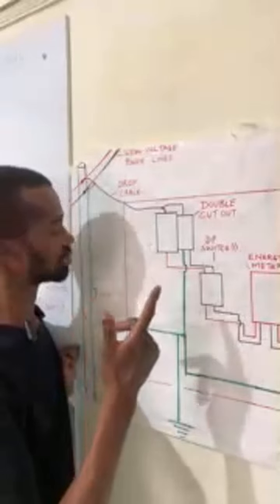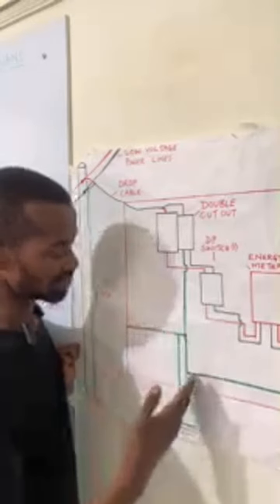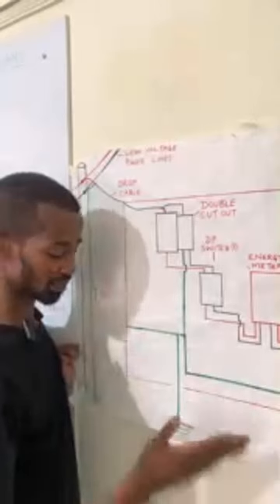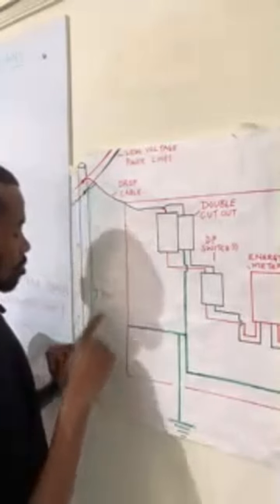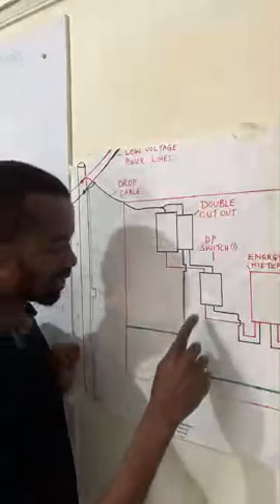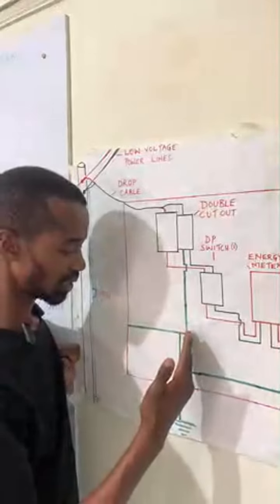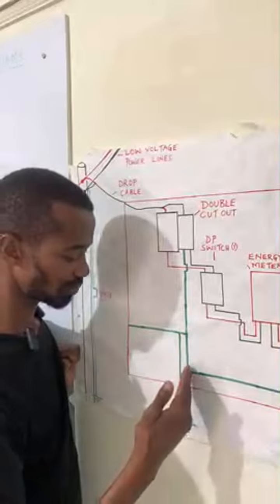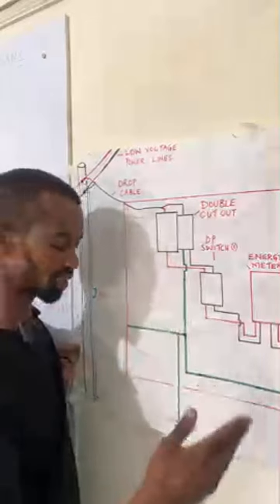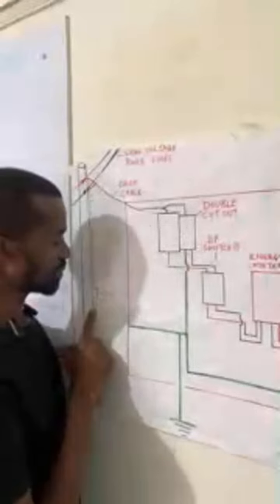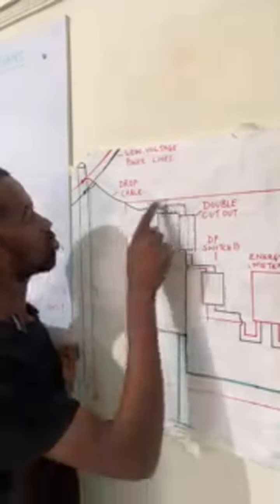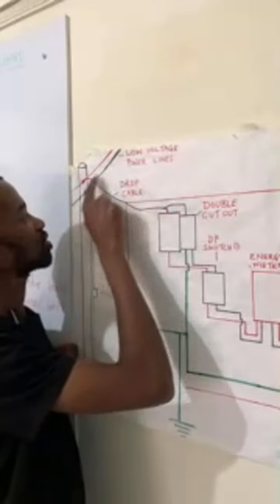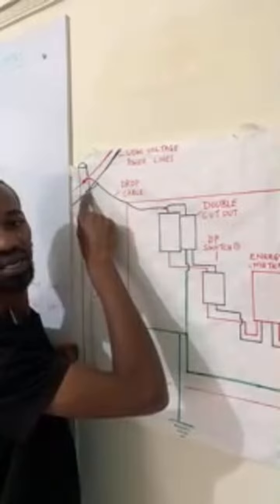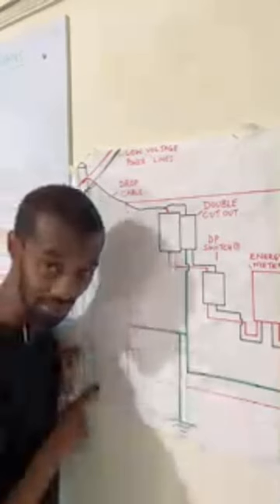I don't know whether you have understood that. So it's just like at this point, we have the meter box earthed separately here, and then we have the PME earthed. So what happens then? What is the relationship between the earthing that is done at the domestic level or at the point where you have that installation, whether single phase or three phase? What is the correlation? Now, this earthing that is bonded at the cutout to this neutral is in connection with this PME, because the neutral is in contact with the conductor that is on the national grid, and this PME is in contact with the conductor at the national grid, dropping to the ground.